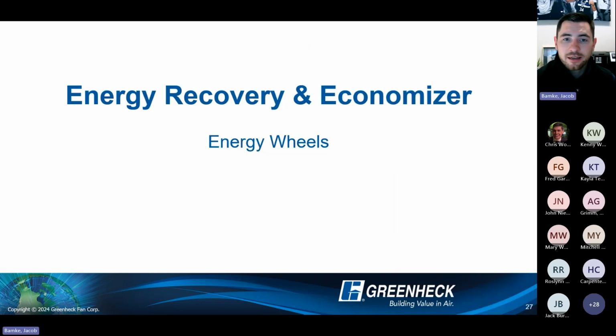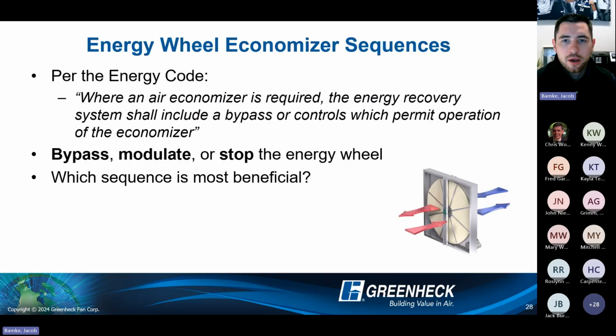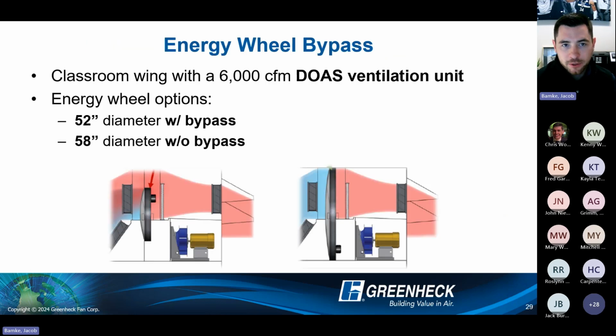All right, and then another efficiency topic that you typically see quite often is the energy recovery and the need for economizer. So if we look at the code, typically it says where an economizer is required, the energy recovery system shall include a bypass or controls which permit operation of the economizer. So a couple options that you have: one, you can bypass the energy recovery device. You can modulate or stop the energy wheel and send air directly through the wheel, but you're not actually using energy to spin it. So which sequence is most beneficial?